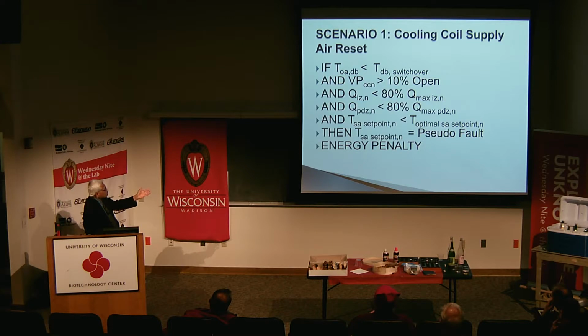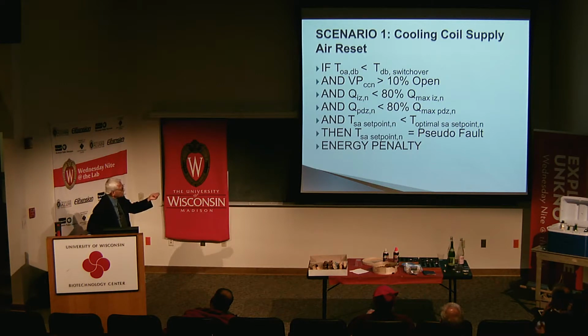If that's the case, if the supply air setpoint is less than what the simulation says should be, then we are saying this is a pseudo fault. You change the set point to a higher level. So again, you have got a cooling energy penalty. So you have got a penalty on it.